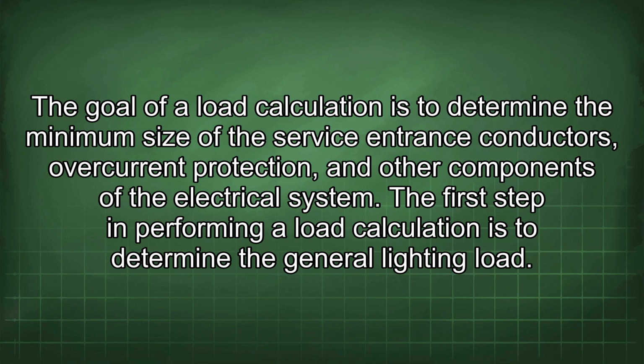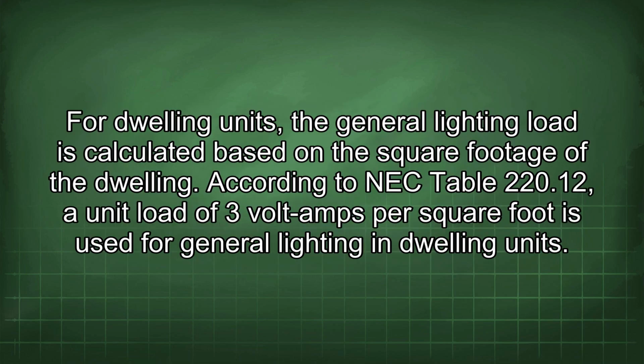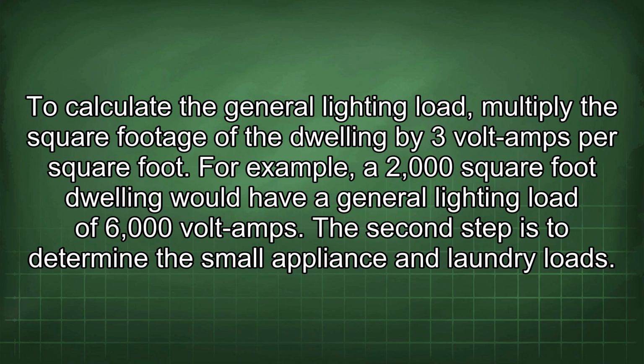The first step in performing a load calculation is to determine the general lighting load. For dwelling units, the general lighting load is calculated based on the square footage of the dwelling. According to NEC Table 220.12, a unit load of 3 volt-amps per square foot is used for general lighting in dwelling units. To calculate the general lighting load, multiply the square footage of the dwelling by 3 volt-amps per square foot. For example, a 2,000 square foot dwelling would have a general lighting load of 6,000 volt-amps.